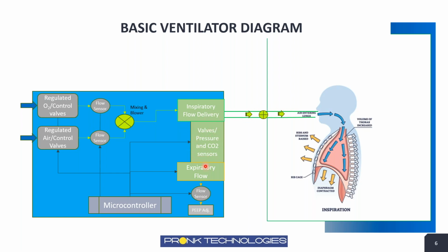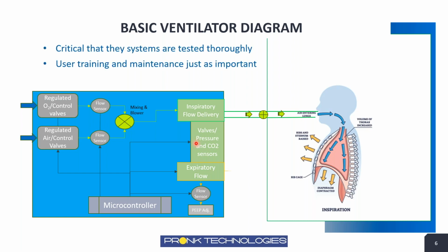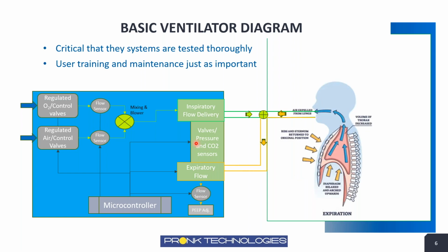Of course, these systems and valves and pressure sensors and CO2 sensors, these are things that are critical to the performance of a ventilator and things that, of course, we have to test during our maintenance, and even clinical staff verifying these sensors are working properly. And then the same is true for the expiratory flow. We have to make sure we're testing these subsystems as the patient's expelling CO2 and air out of the lungs, which flows back through the ventilator through the expiratory flow and flow sensor to monitor that. And of course, you have other systems in there that allow us to control that expiratory pressure through our PEEP adjustment, our positive end expiratory pressure controls here, so we can basically provide the therapy to the patient as needed.